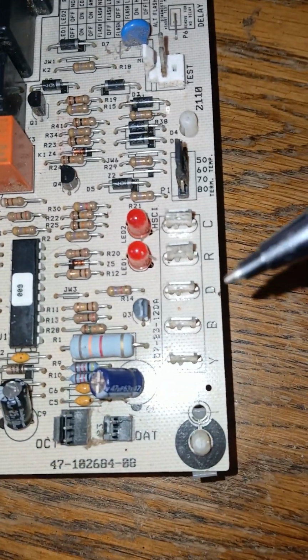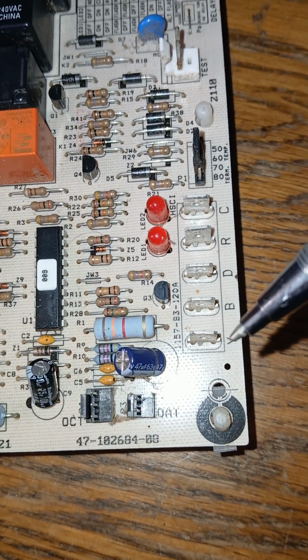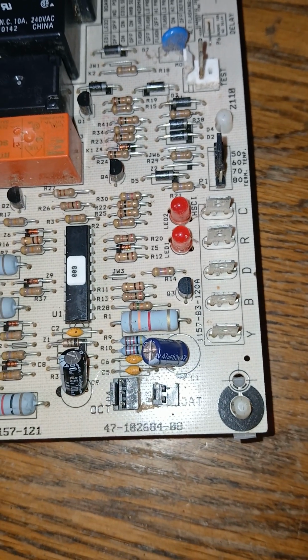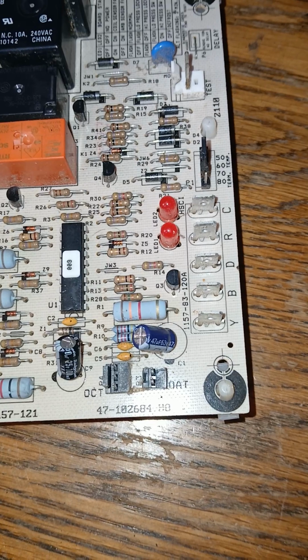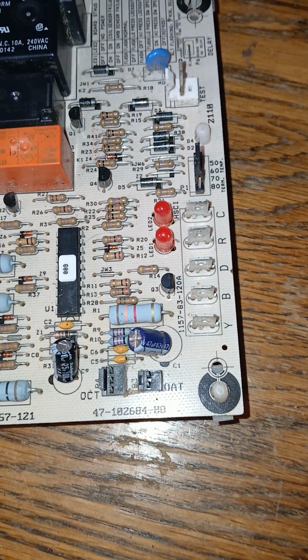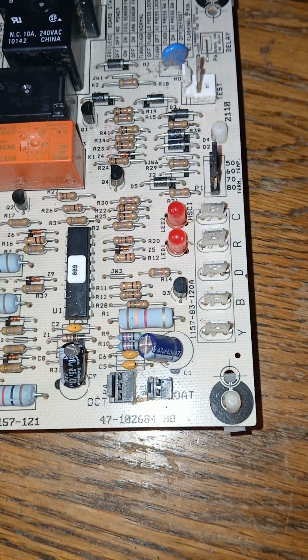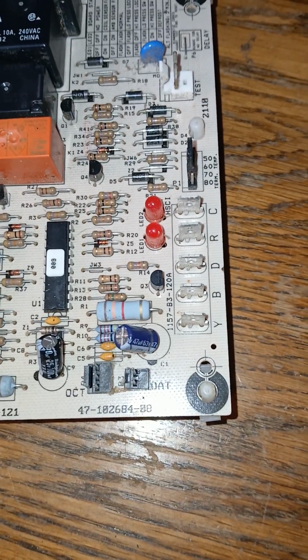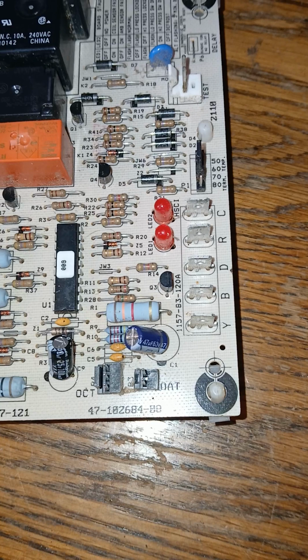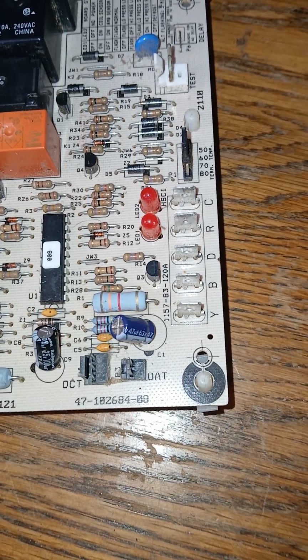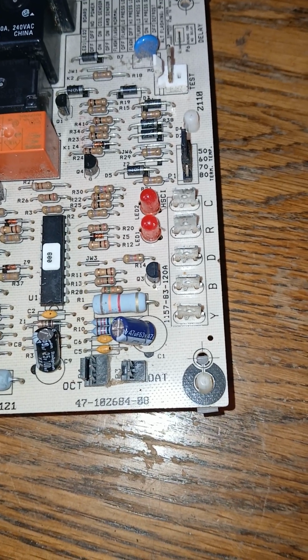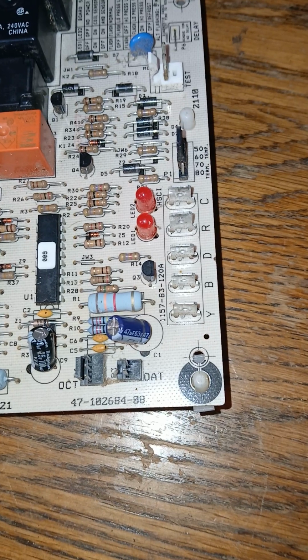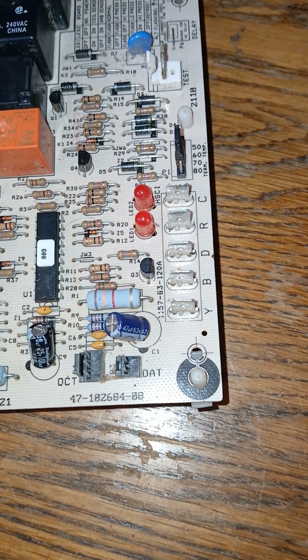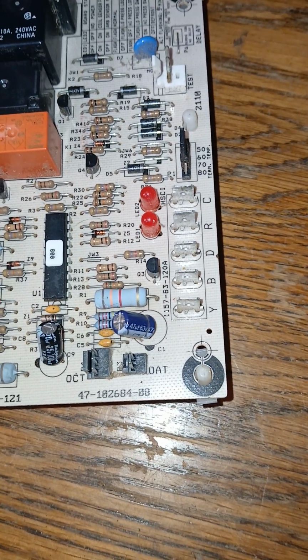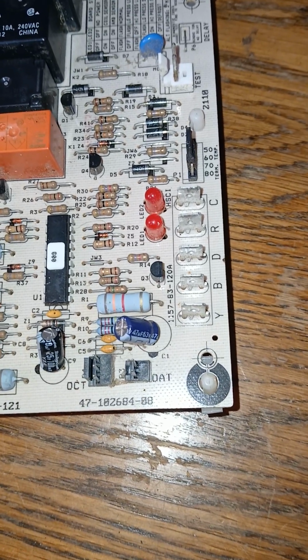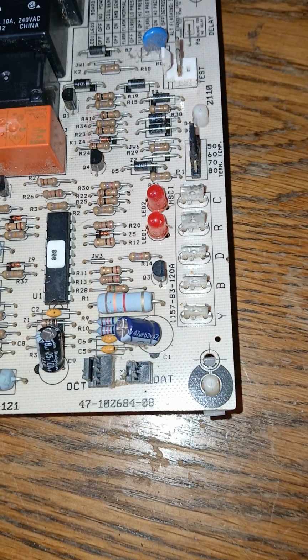So we've had the red, the C, and the Y, and then once the Y is energized, it should go out and energize either the cooling mode or perhaps the heating mode. It depends on what happens with the reversing valve. If it's put into heating mode, then at that point the outside unit would become like the inside unit, and the inside unit would become like the outside unit, meaning that the A coil on the inside essentially would be flip-flopped. You would take and flip it 180 degrees. So this is kind of theoretically how a heat pump works.